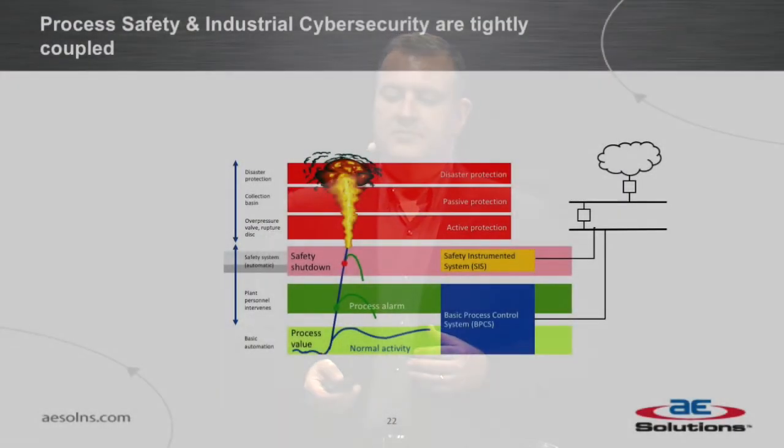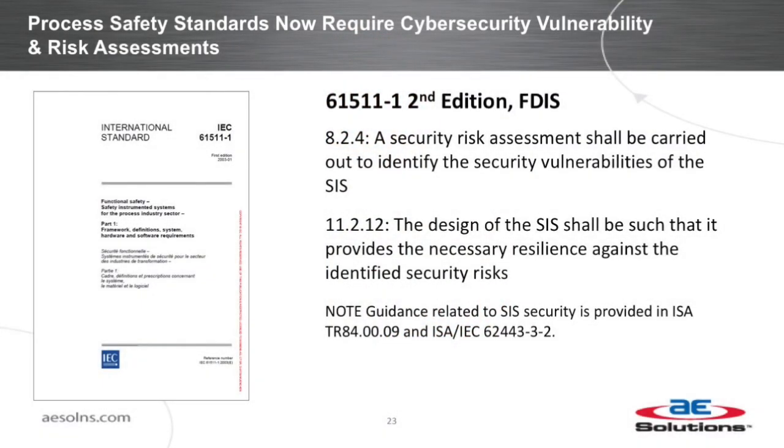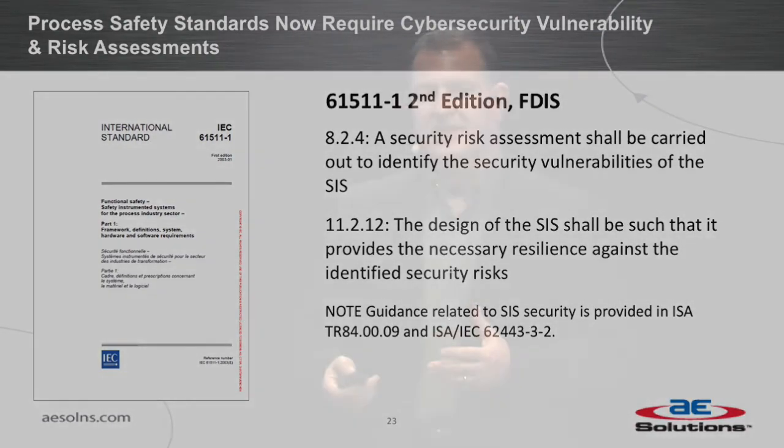Going back to the earlier diagram, we have the basic control system and the safety system, but in reality today those are oftentimes networked together with common HMIs, common engineering workstations, and common networks. So it's possible that a single threat actor could potentially attack both the control and the safety system — either initiating an event or preventing a safety action from bringing the process to a safe state. The safety standards have also recognized this — IEC 61511 is the predominant one for functional safety, and the latest version does recognize that a security risk assessment needs to be carried out because safety assessments are limited to random or systematic failures, not cyber and not deliberate. The design of safety systems now needs to provide resilience against cyber threats as well.